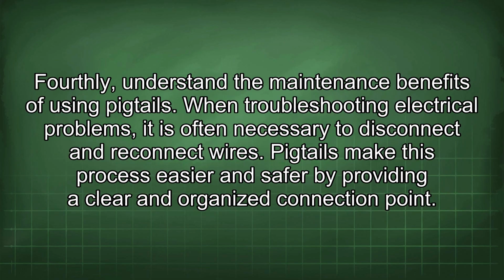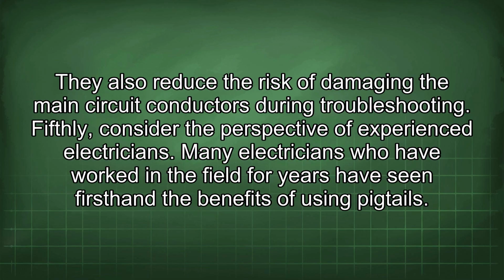Fourthly, understand the maintenance benefits of using pigtails. When troubleshooting electrical problems, it is often necessary to disconnect and reconnect wires. Pigtails make this process easier and safer by providing a clear and organized connection point. They also reduce the risk of damaging the main circuit conductors during troubleshooting.